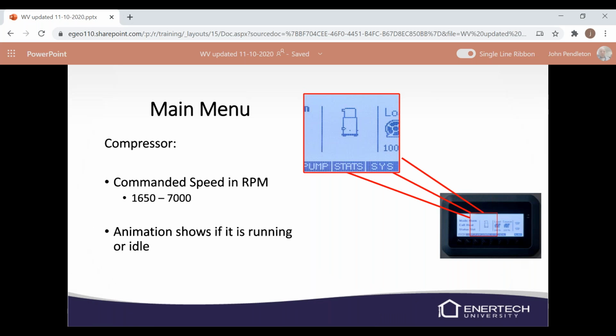The main menu will show this little compressor animation, basically. Underneath it, if the compressor is calling, it'll show the operating range. And sometimes it might be based on your outdoor reset, it might be, you know, 1650 to 4500 RPM. So it'll list that, and then it will also list, if your compressor is running, what RPM it's running at right now. There's also some black bars that will run up and down this little compressor looking thing in the picture and show that the compressor is running.